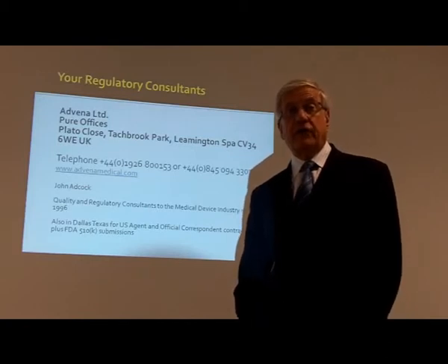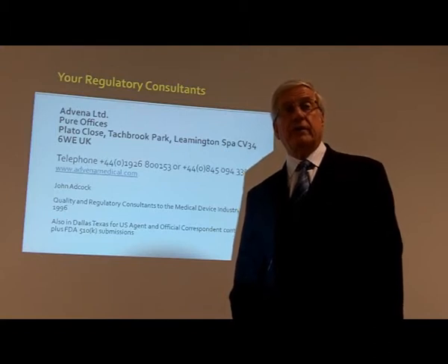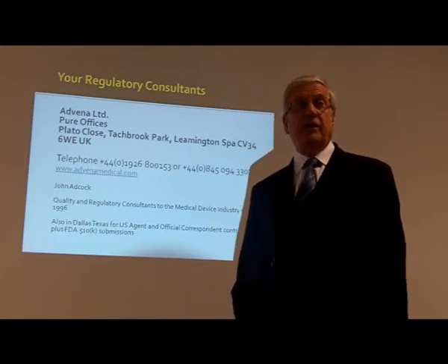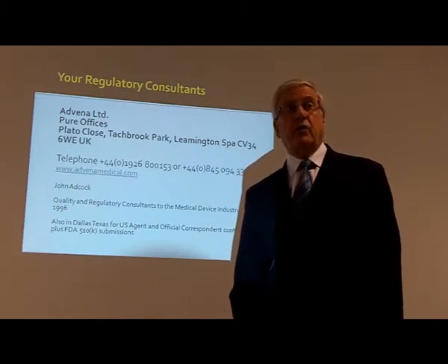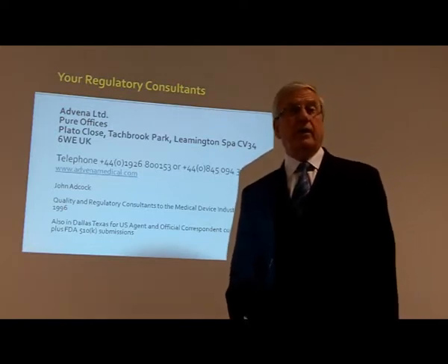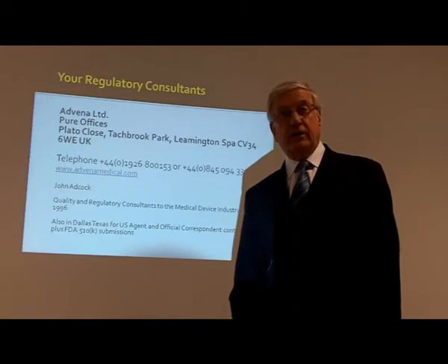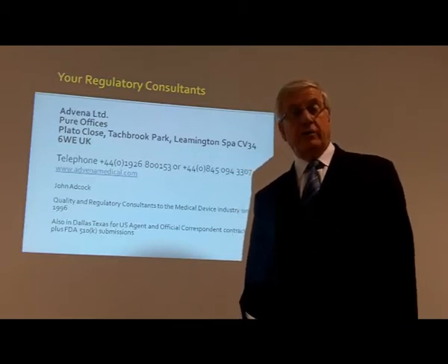The regulations we're concerned with are the Active Implantable Medical Device Directive. This concerns, of course, as it says, just devices like pacemakers and the like. And there's the Medical Device Directive, which is the all-encompassing directive, which most people are concerned with, and the In Vitro Diagnostic Directive, which concerns devices that are for testing in vitro of the body, outside of the body.